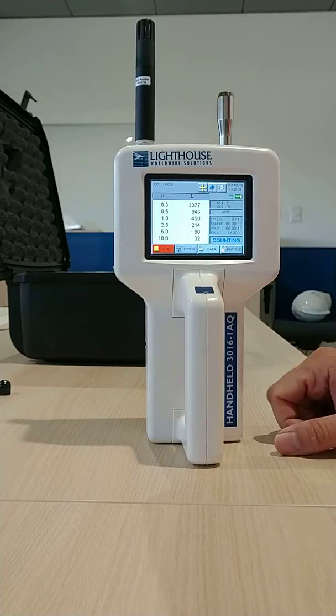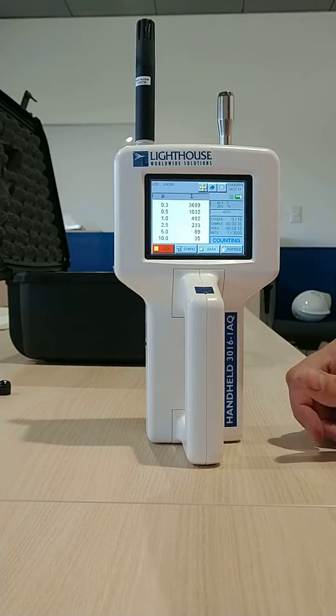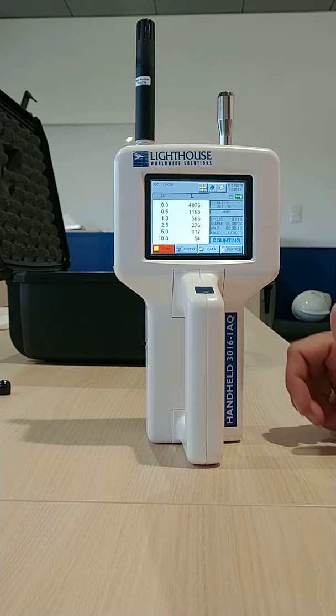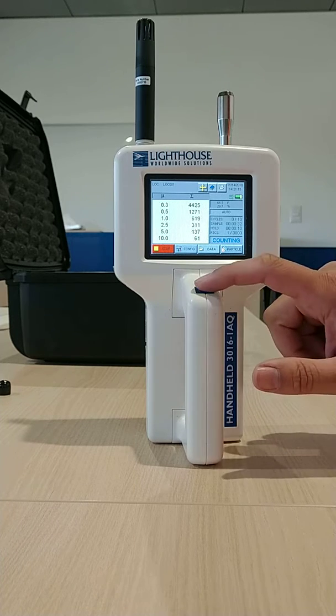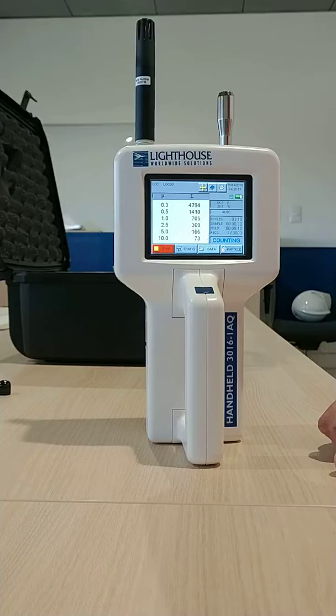When you go through the menu, it's going to record the data and store every 1 minute. So when you want to stop, you just press this button again to stop recording data. Otherwise, it'll just record data forever. When the clean room is running, all of these should be pretty close to zero. You can see we're already at 6,500 counts at the 0.3 micron size of particles.